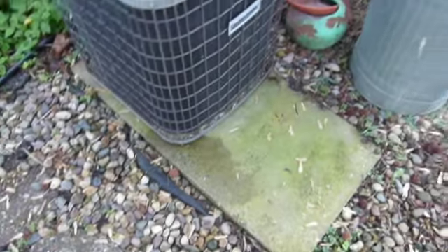Look in there — you can definitely see there's a bit of a problem. That poor compressor's covered in ice. So too is this. That's a good way to have something bad happen to a compressor right there.